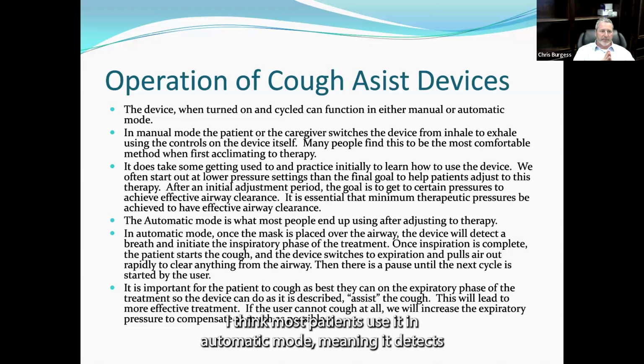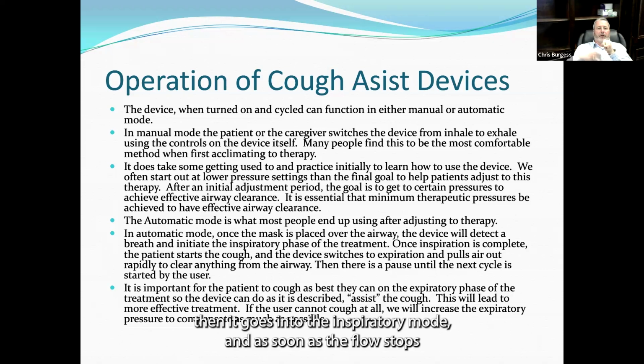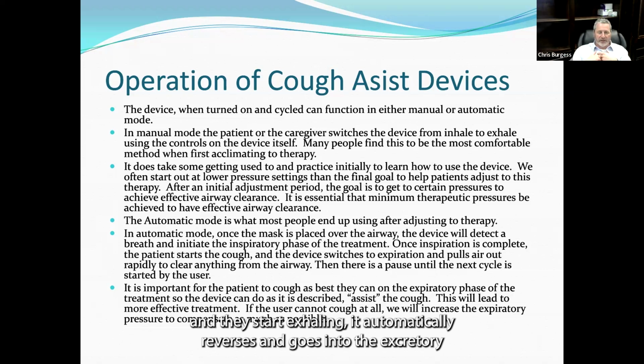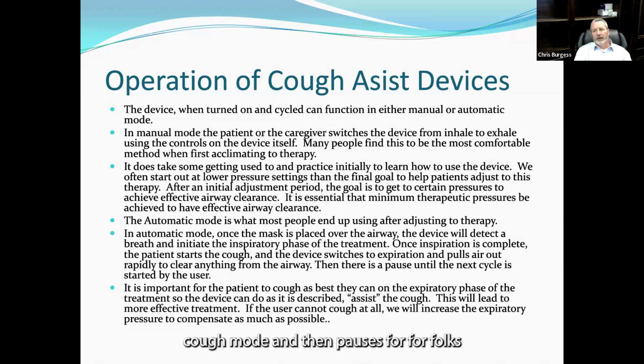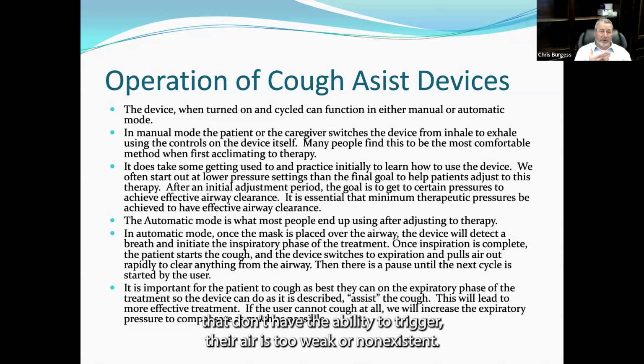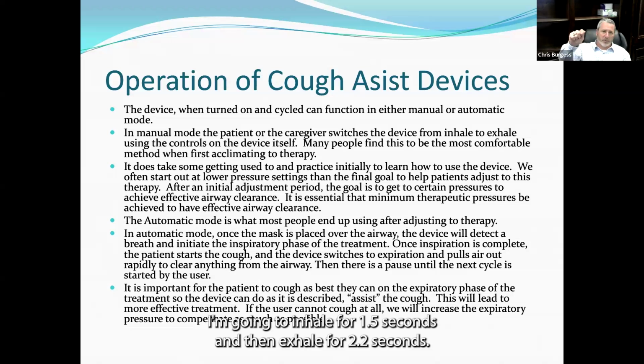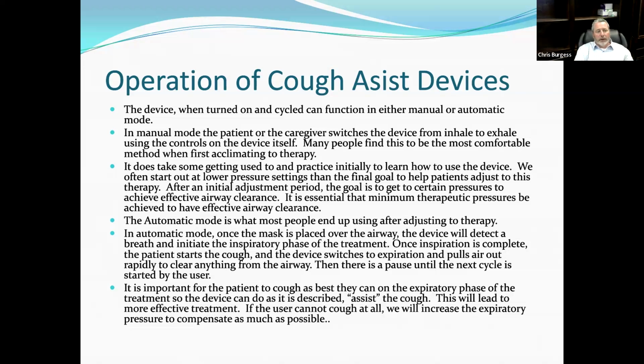I think most patients use it in automatic mode, meaning it detects when I take my deep breath. When it detects the patient's breathing, it goes into the inspiratory mode. And as soon as the flow stops and they start exhaling, it automatically reverses and goes into the expiratory cough mode and then pauses. For folks that don't have the ability to trigger it, because their airflow is too weak or non-existent, the automatic mode can just be set to default times. I'm going to inhale for 1.5 seconds, exhale for 2.2 seconds, and pause for 1 second, and it'll just cycle as many cycles as programmed into it. I generally recommend 3 inhales, 3 exhales, then a pause, and then do 3 more, then a pause, and then do 3 more. 3 sets of 3.